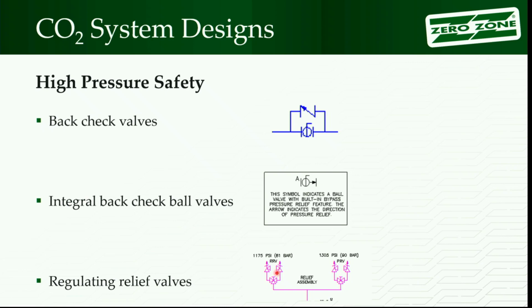You're going to keep burping, burping, burping. Hopefully you never release the mains on there unless you'd have a fire with that. All of these have relatively low pressure closing forces, right? Your check valves may be magnetic, may be lightly spring loaded, so there's not a lot of closing force. The safety valves, when you're up near this design pressure, there's not a lot of closing force on it.